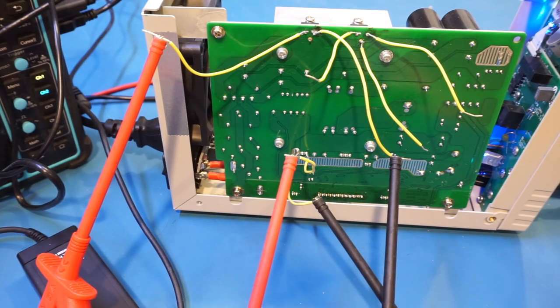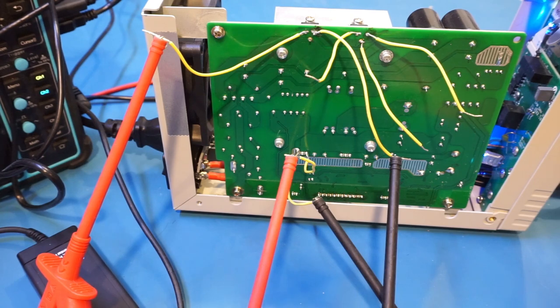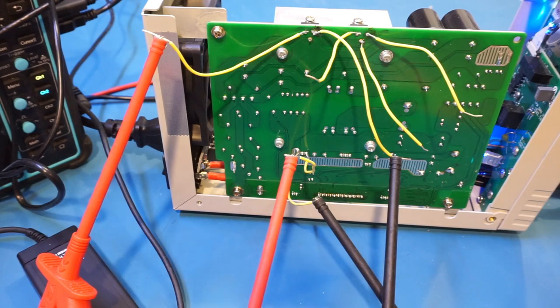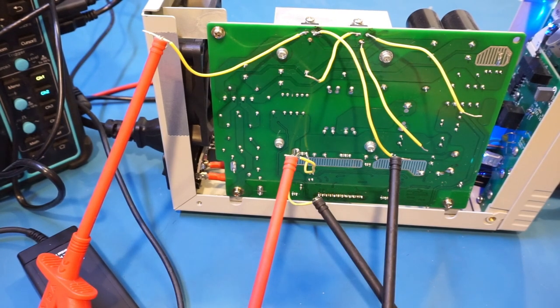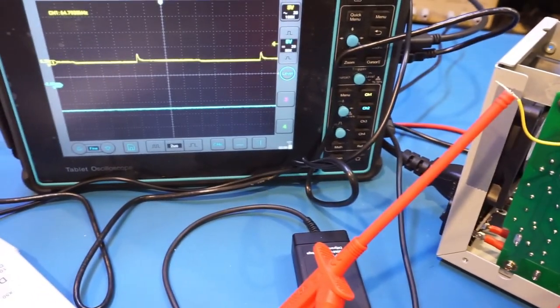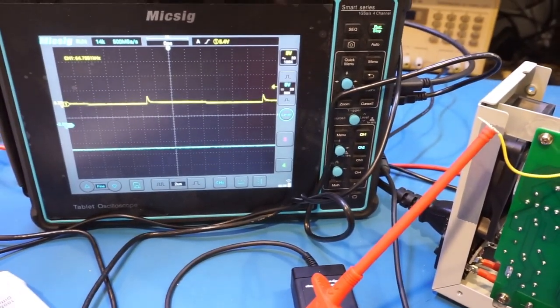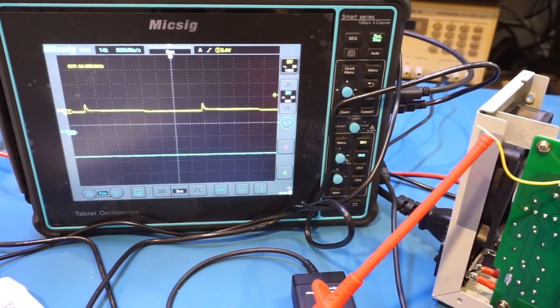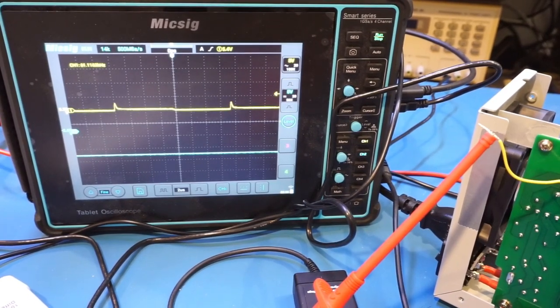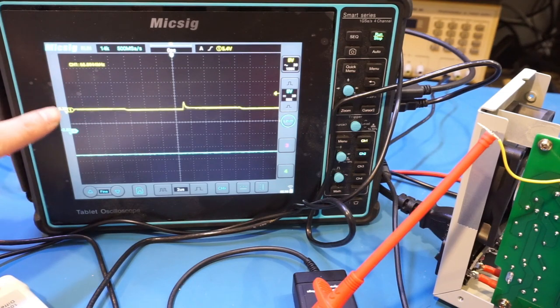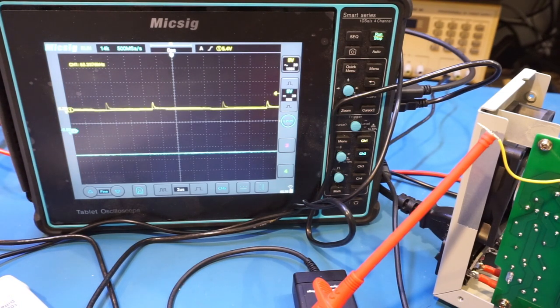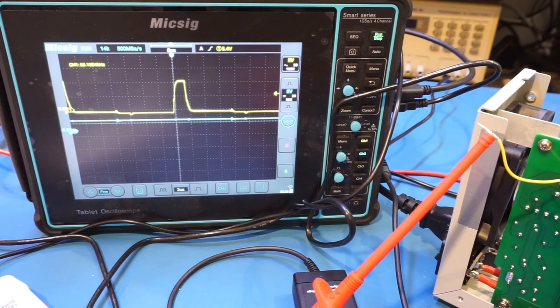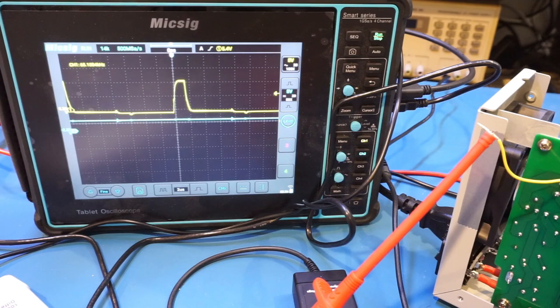And while we still have access to the circuit board of the power supply, I do want to verify what that MOSFET on the second heatsink is doing. As we suspected, that is for switching the output on and off. But let's verify that. So again, I hook up channel 2 to that MOSFET's gate. And you can see here, when the power is off, the cyan trace is showing that the gate was pulled low. And let's enable the output. And as we suspected, when we turned on the output, the MOSFET was switched on.